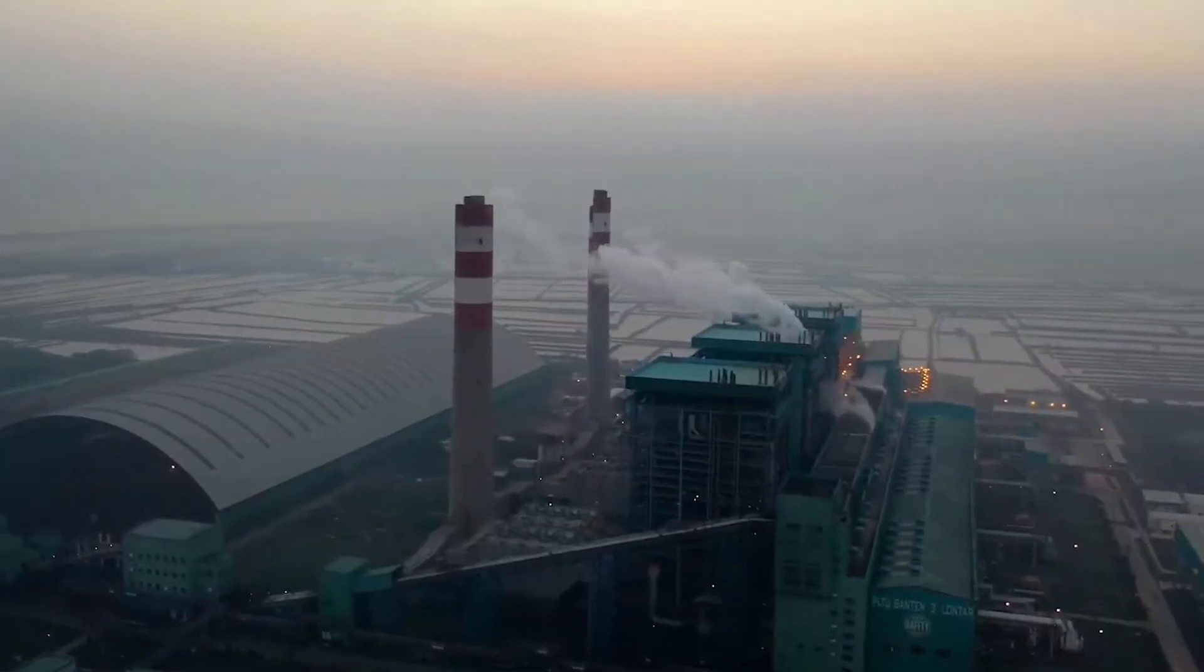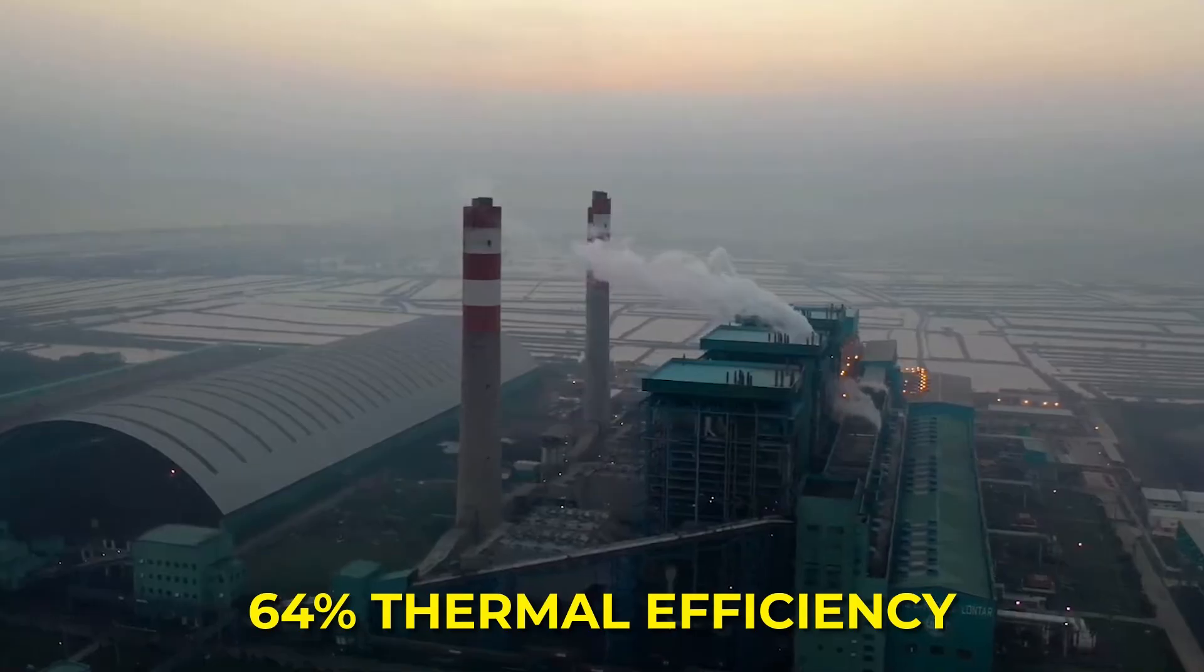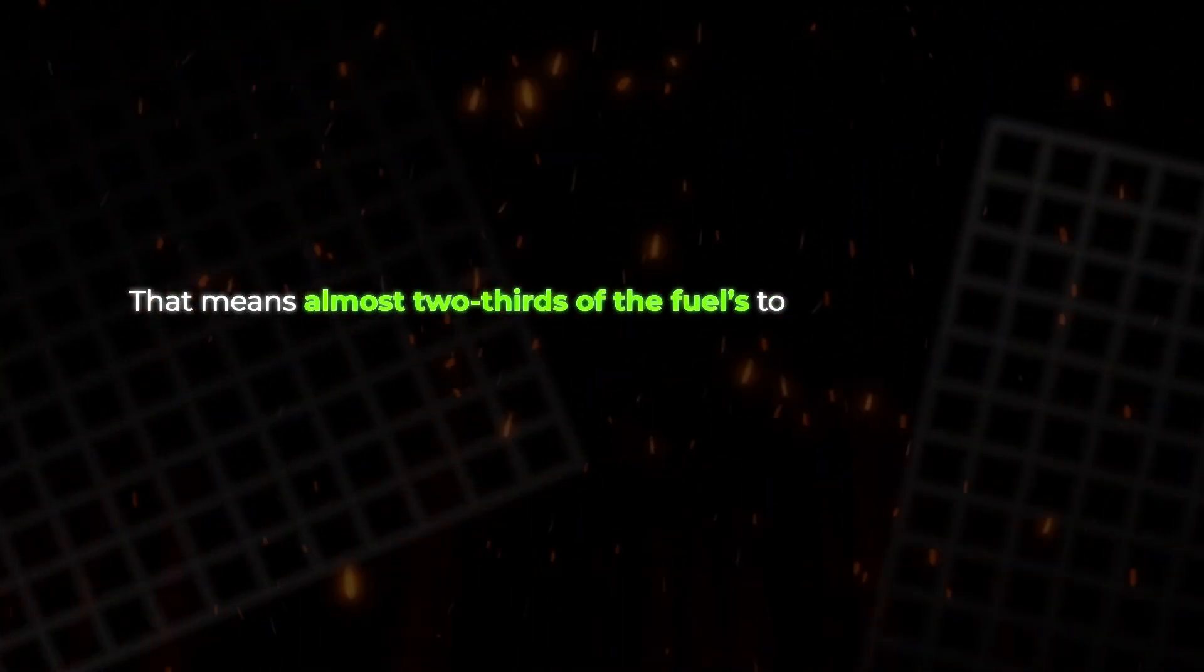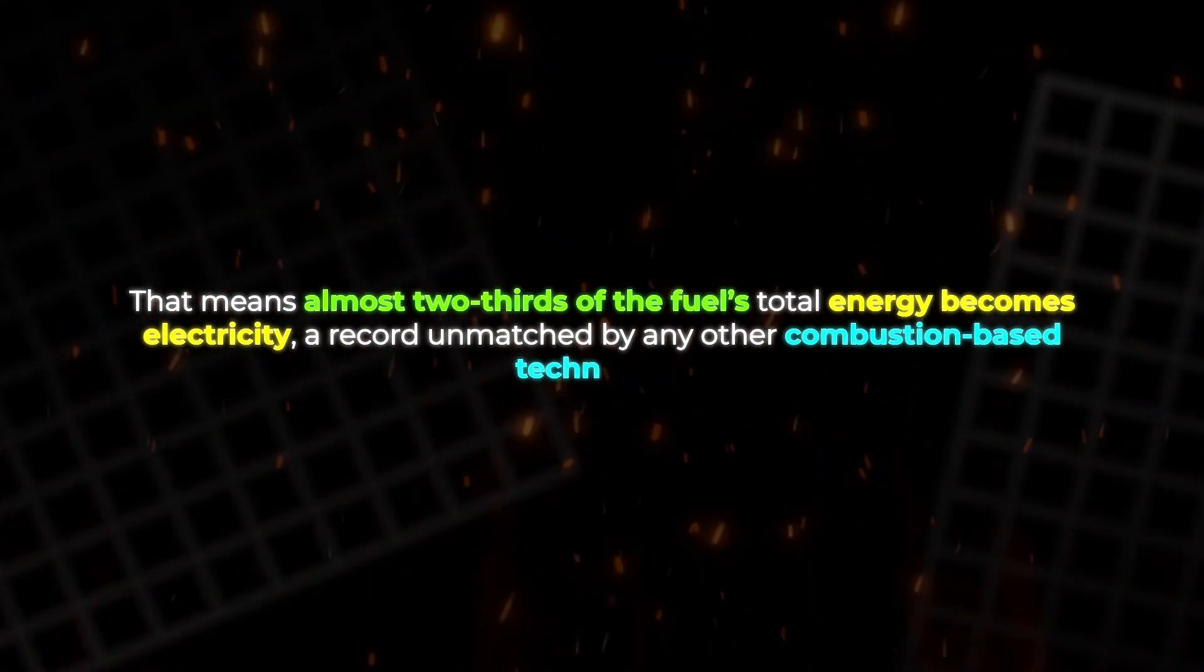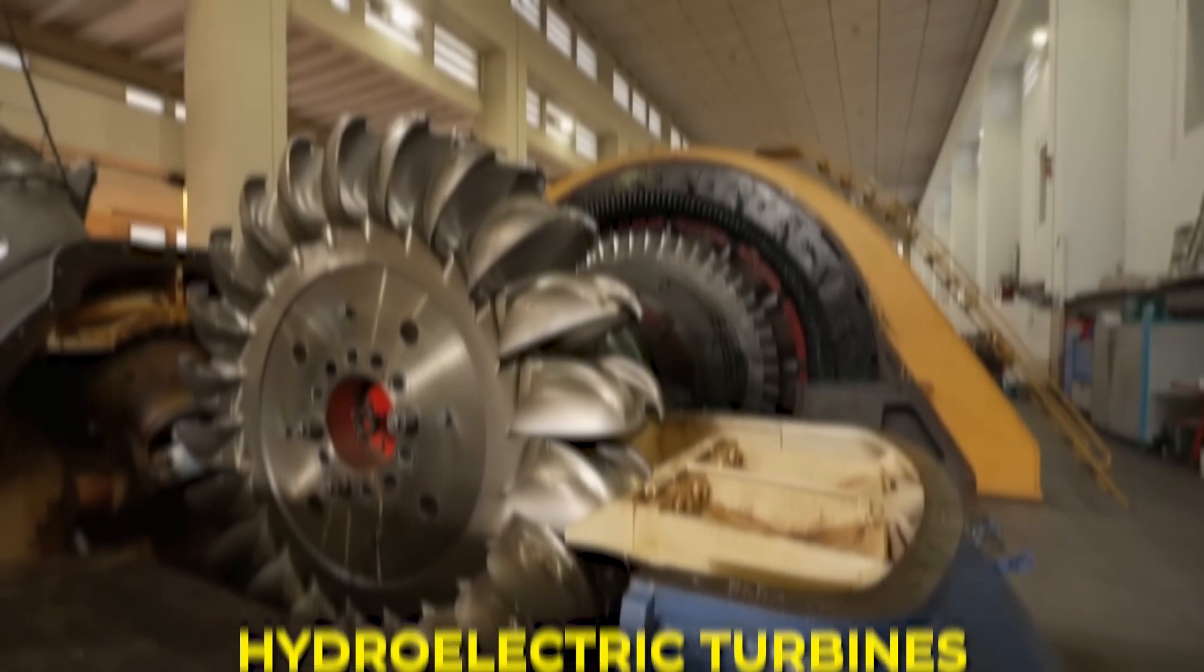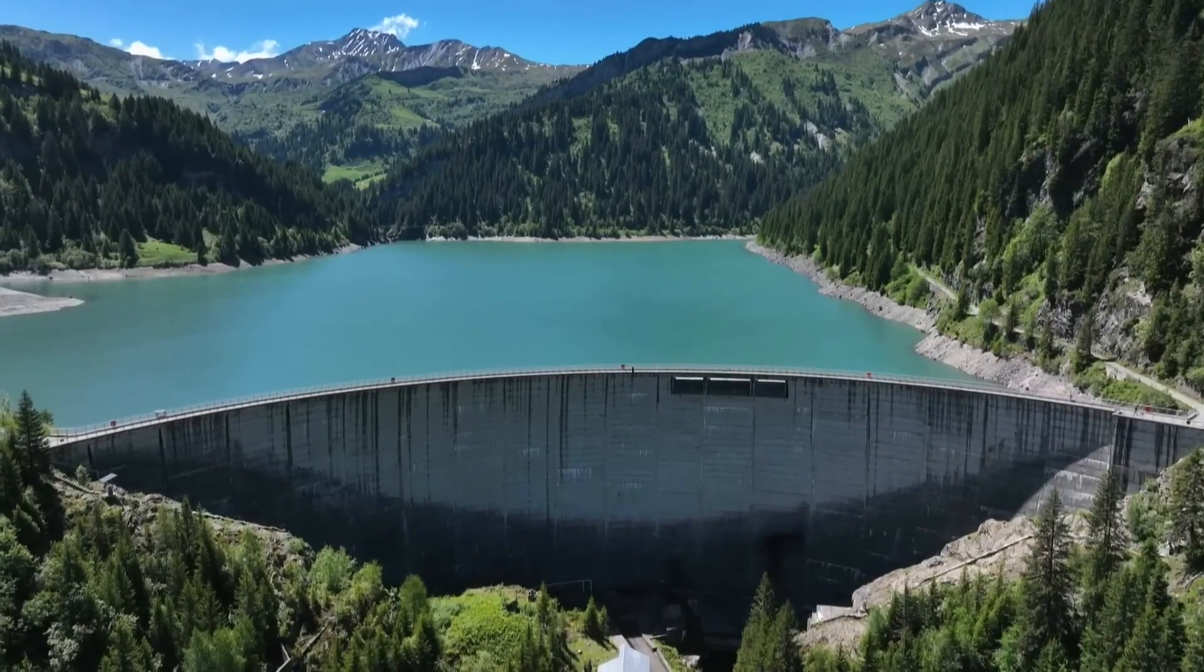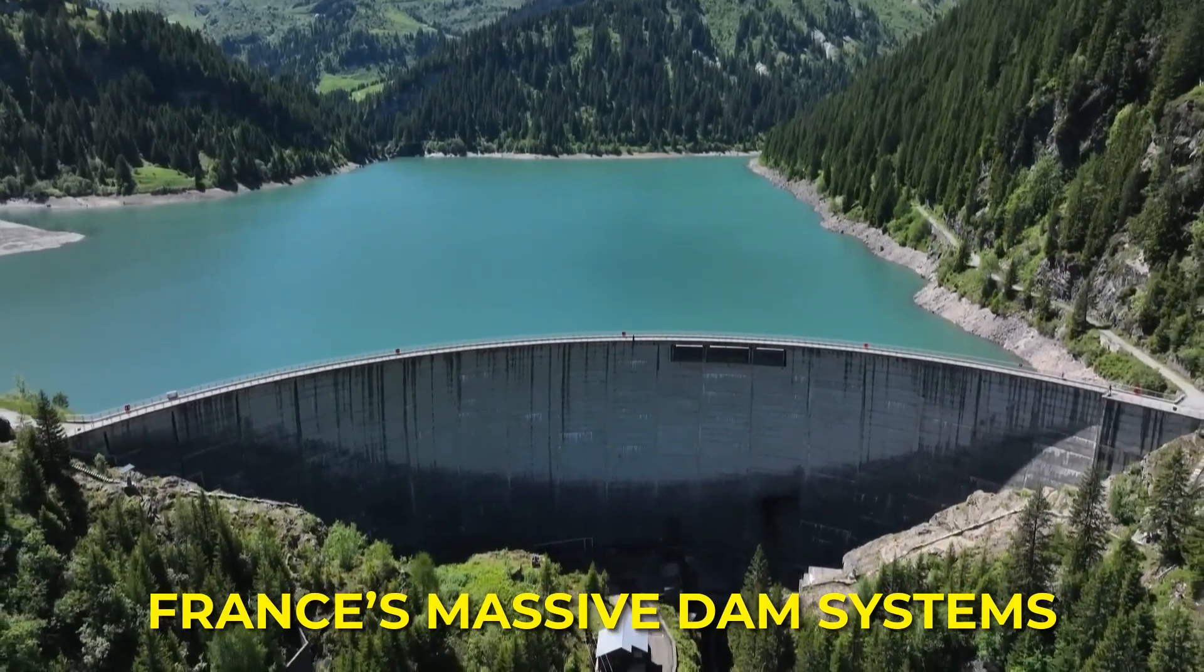This integration pushes overall plant efficiency to astonishing levels. The best modern combined cycle plants can reach around 64% thermal efficiency. That means almost two-thirds of the fuel's total energy becomes electricity, a record unmatched by any other combustion-based technology. Only hydroelectric turbines, like those used in France's massive dam systems, operate at slightly higher efficiencies.